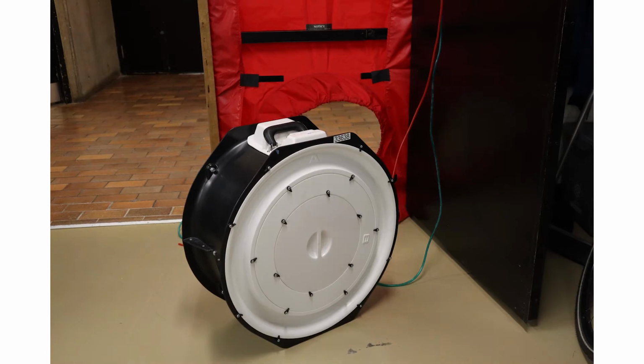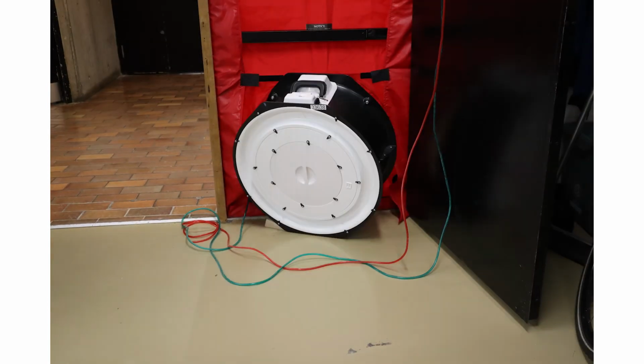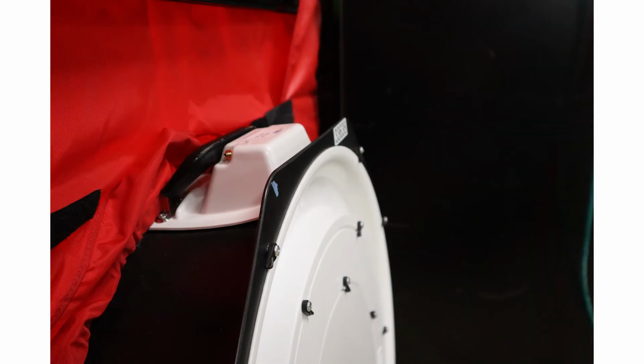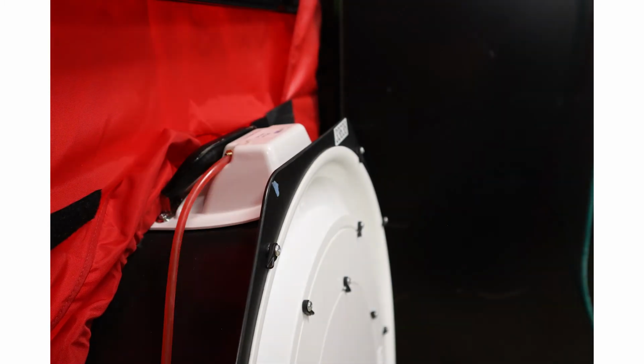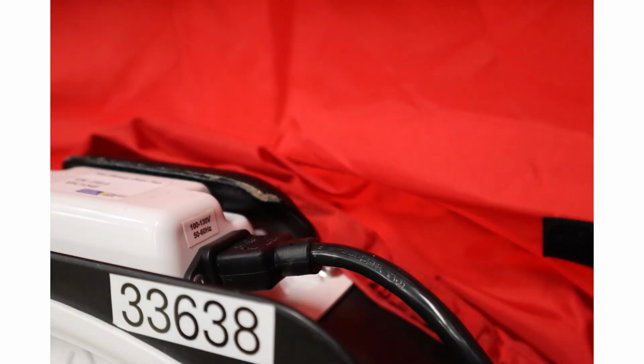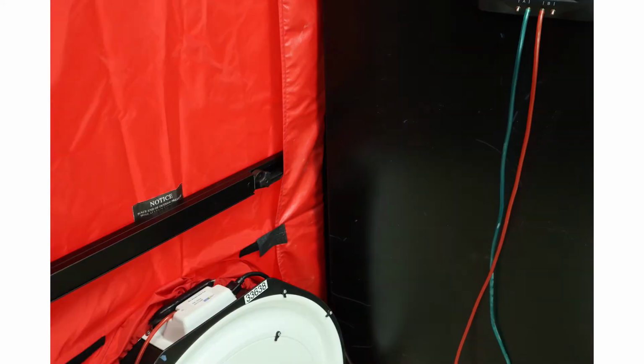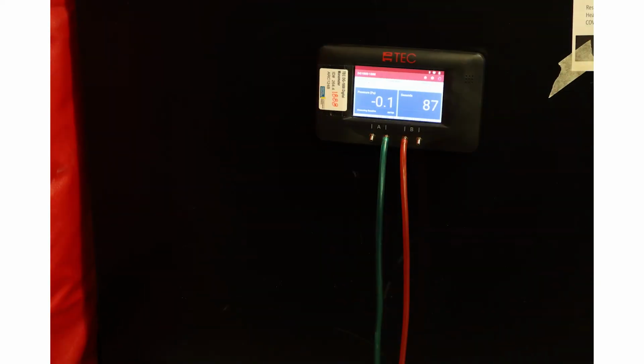Place the fan onto the fan hole, ensuring that there are no gaps between the membrane and the fan. The other end of the red tube is inserted into the fan port and the fan can be plugged in. We are now ready to test. Before the test can begin, the fan should be closed and the pressure should be measured. This accounts for ambient wind and environmental conditions. This is known as the opening pressure.